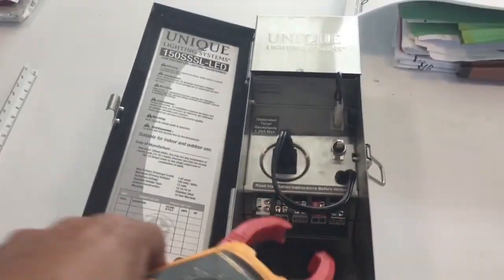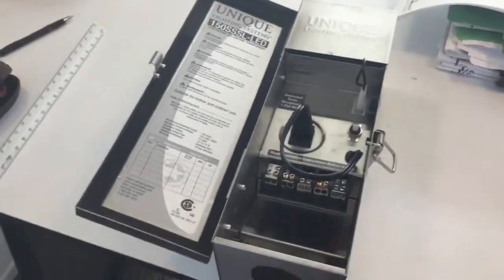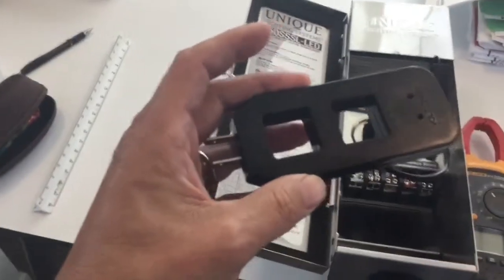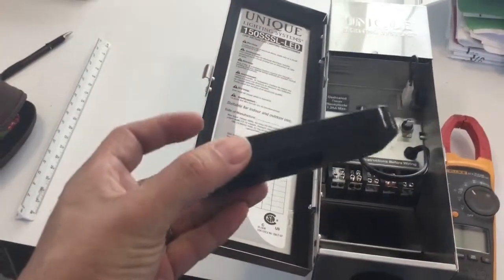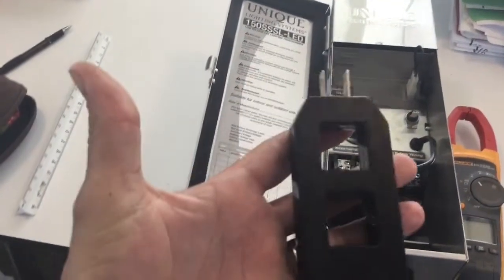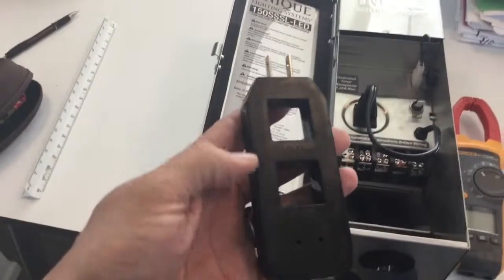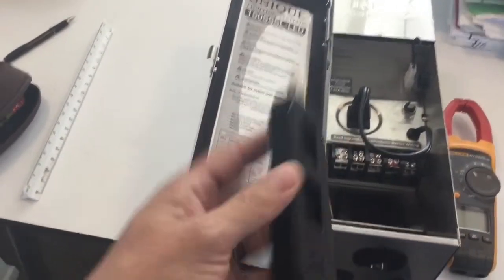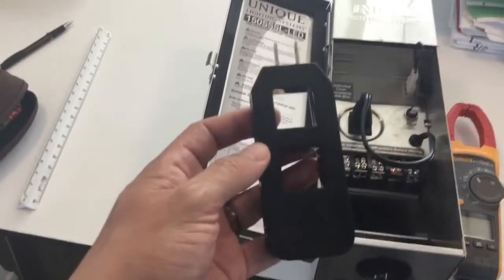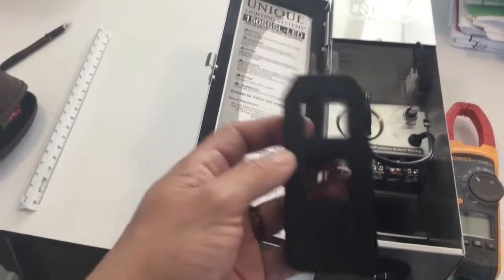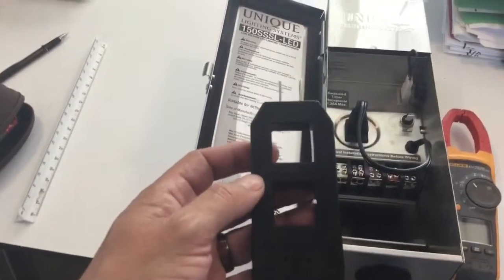Now, if you've got a transformer that isn't Unique Lighting, or it doesn't have any of these features to be able to test it, what you need to do is run down to your local hardware store and get yourself a line splitter. There's different varieties out there. I grabbed this one from Ace Hardware the other day. It's only about 15 bucks, but this is a great tool to help you decide what your reading is or what your amp load is on your transformer.